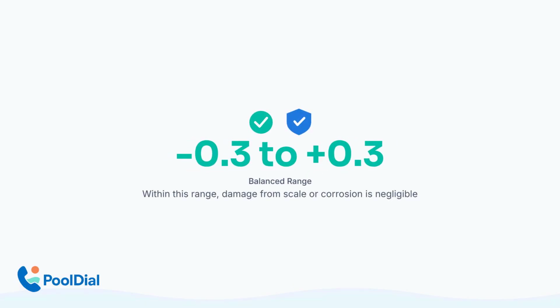The accepted balanced range is negative 0.3 to positive 0.3. That's your target window. Within this range, the water's tendency toward scale or corrosion is negligible. Outside it, damage accumulates over time.